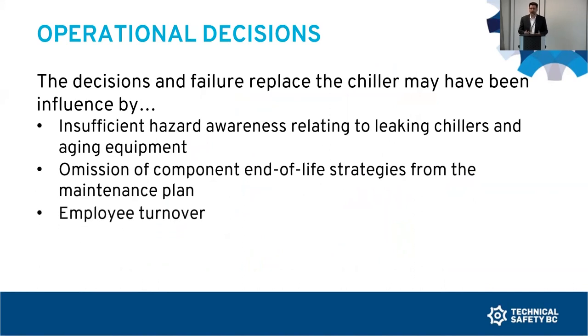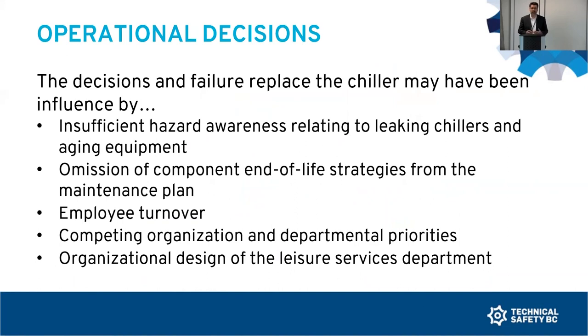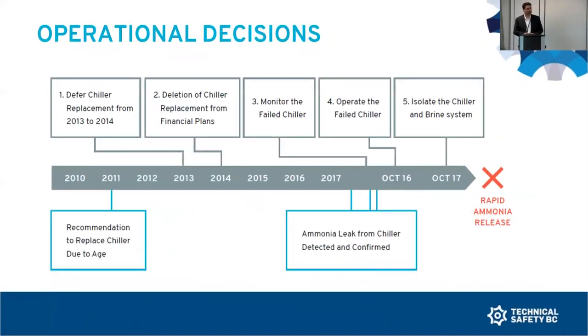So as I mentioned before, it's so important not to just look at the parts that failed and how they were touched last in order to really understand how an incident unfolds. We did find a number of operational decisions that contributed very much to this incident occurring. Throughout, there was insufficient hazard awareness relating to leaking chillers and aging equipment, and a predominance of operation and run to failure within industry. We found here, and also in industry, that end-of-life strategies for many components aren't part of the maintenance plan, so people aren't necessarily planning for those large expenses. They come about due to failures. There was also employee turnover and a number of competing organizational priorities that contributed to decision-making that left this aging chiller in continued operation, and also its use after a failure was detected.